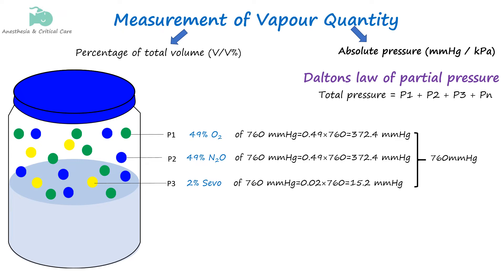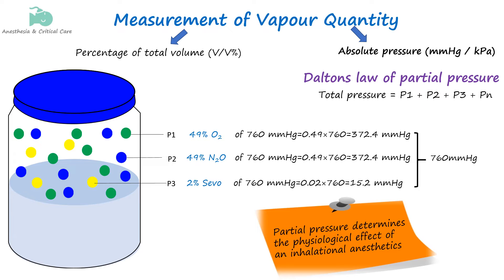These concentrations are determined by a gas analyzer in the anesthesia circuit and can also be ascertained from the vaporizer dial. The partial pressure of the anesthetic agent determines its physiological effect, as the agent's partial pressure drives its absorption into the bloodstream and tissues. When we adjust the concentration on the vaporizer dial setting, we are indirectly adjusting the partial pressure of the anesthetic agent relative to oxygen and other gases.